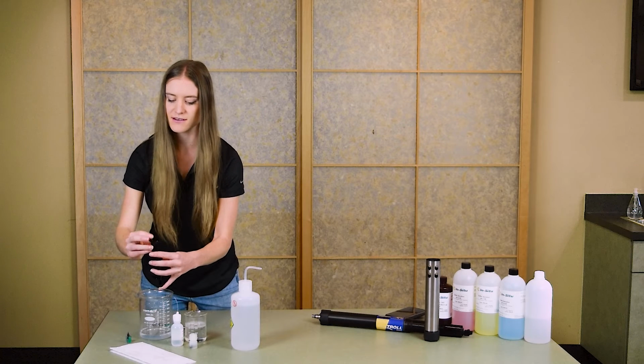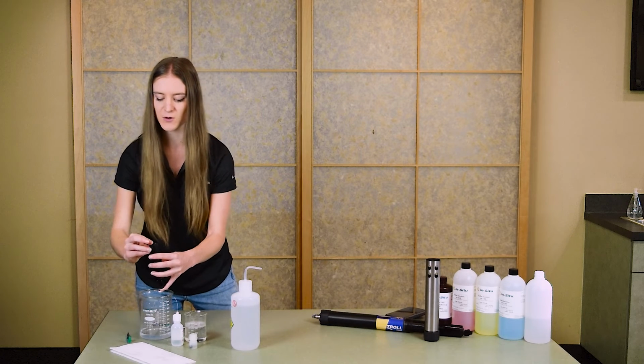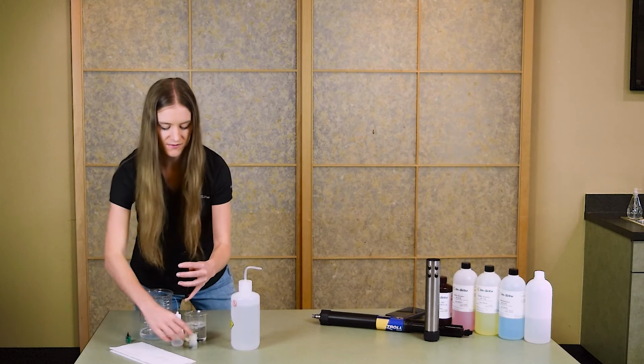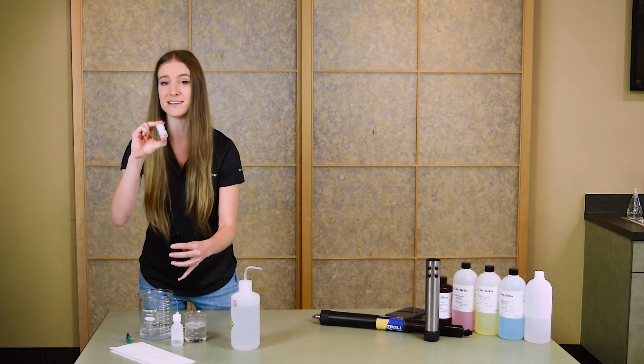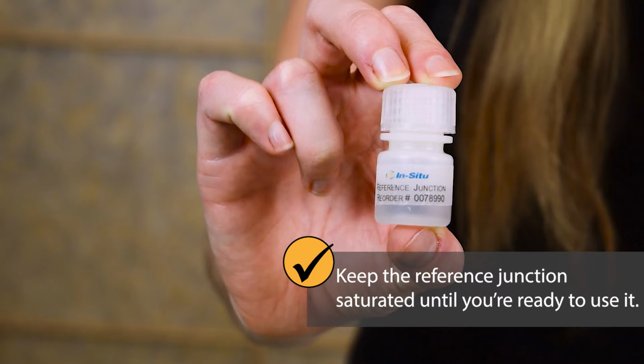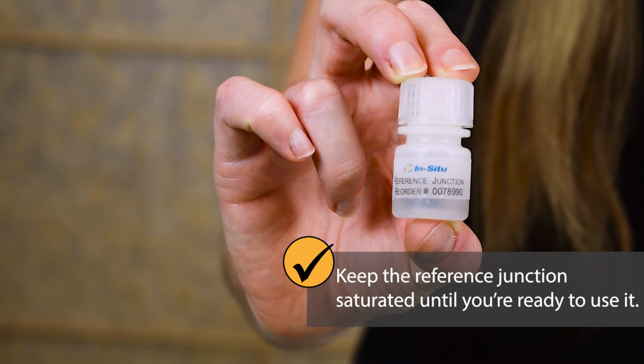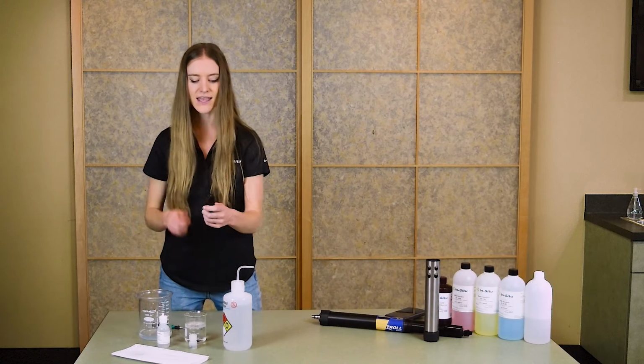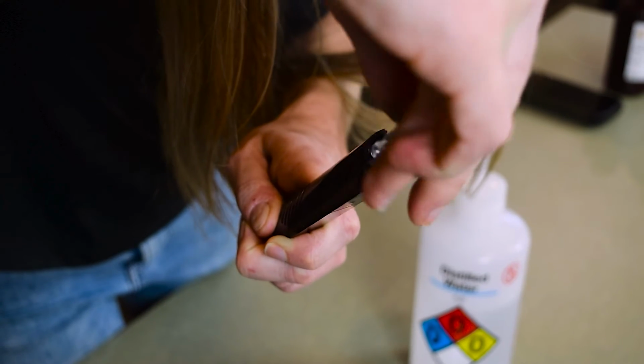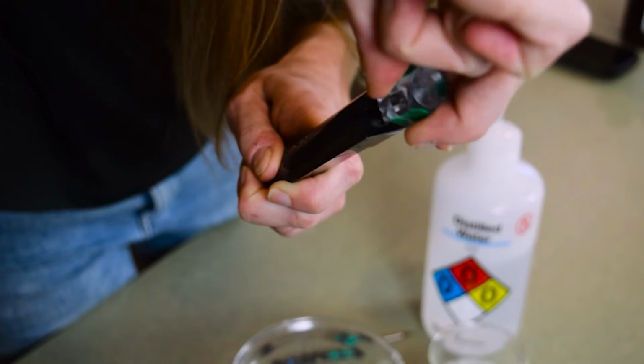If you've noticed that there's a lot of calibration errors or you've performed this process several times, you can replace it with a fresh reference junction, which you can order from In-Situ. Always keep your fresh reference junction saturated in solution until you're ready to use it. Tighten the reference junction until it touches the sensor body, and then tighten it 1/4 turn more to secure.